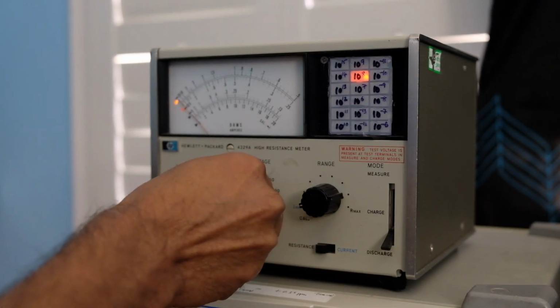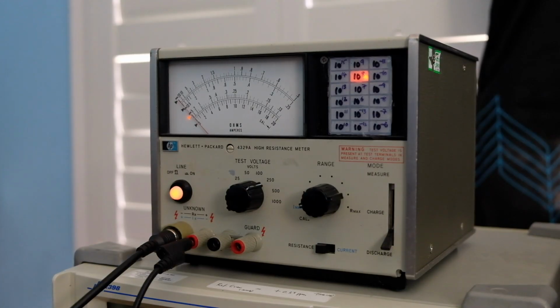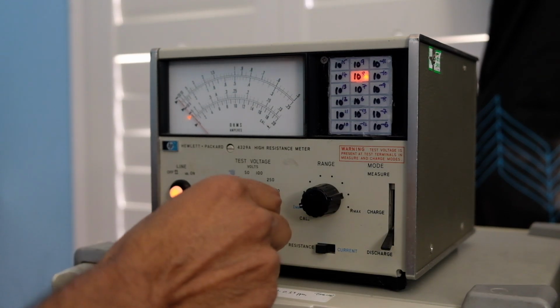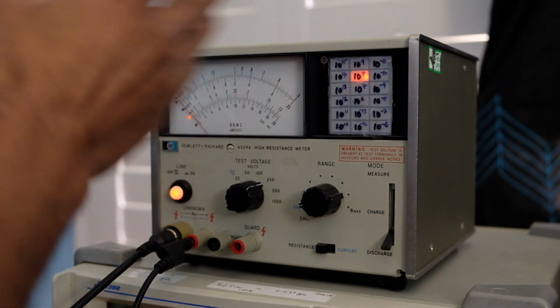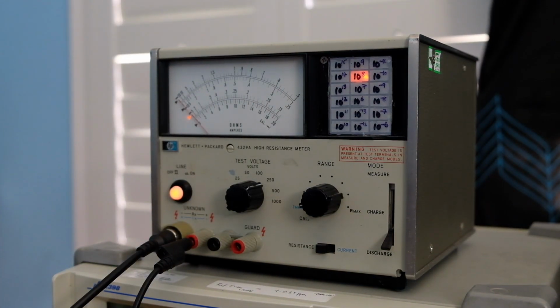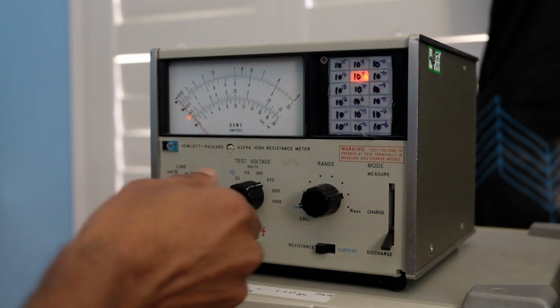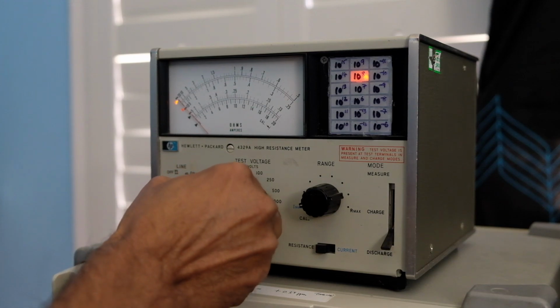The other thing I found was when I went into the 500 or 1000 volt range, there was a kind of a buzz coming out of the instrument, and when I opened it up, I found that one of the wires connecting into a shielded area of the instrument was arcing. That was making the buzzing sound, and the reading was fluctuating heavily because of that poor connection, basically the leakage from the test voltage going into the test device. So I cleaned that up, put proper insulation, and re-wired it, and now it's working perfectly over all the ranges.